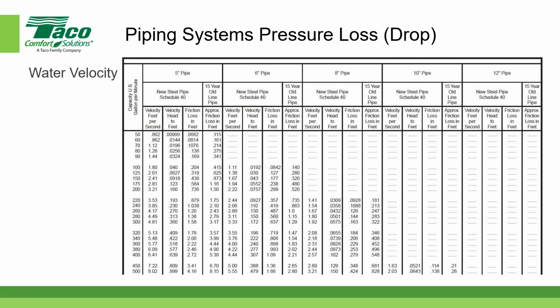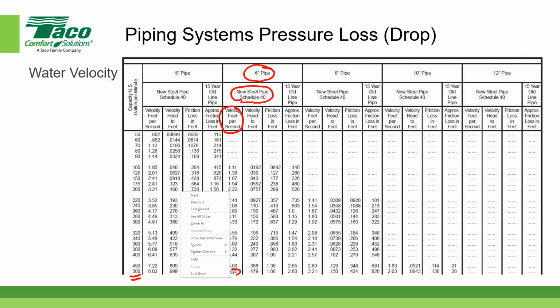All right, hopefully this will still work. Oh yeah. So here's a little table that I downloaded from the internet. These are readily available. And if you'll notice, for our example here, we have 6-inch pipe. And we said that we had a flow of 500 gallons per minute, which we have over here on the left-hand side. And it is, again, Schedule 40 steel pipe. And if you'll notice, under the column where it says velocity in feet per second, that's this little column right here, that they are publishing a value of 5.55.